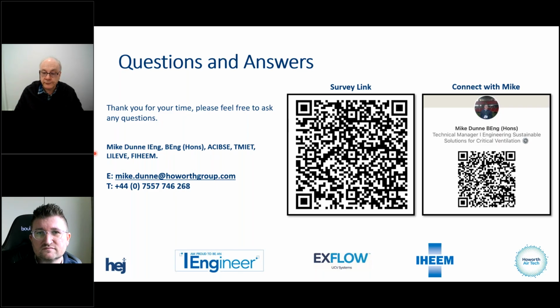No doubt conscious of costs and carbon savings, some trusts are switching off theatre ventilation at night, one attendee says, and asks, can your canopies be turned off safely or should they remain in background mode? No, we can turn the canopy off. One thing that you need to be careful of if you're leaving the UCV on and switching the HVAC system off is that heat gain that I spoke about. We have a heat gain that's coming from the canopy. And with no HVAC in there, you're going to really push the temperatures up inside the operating theatres.